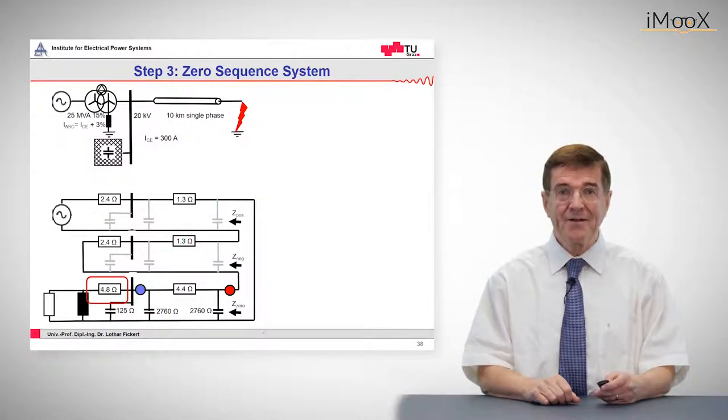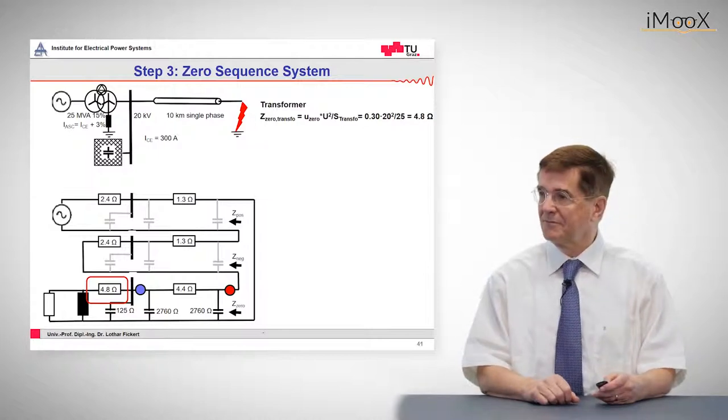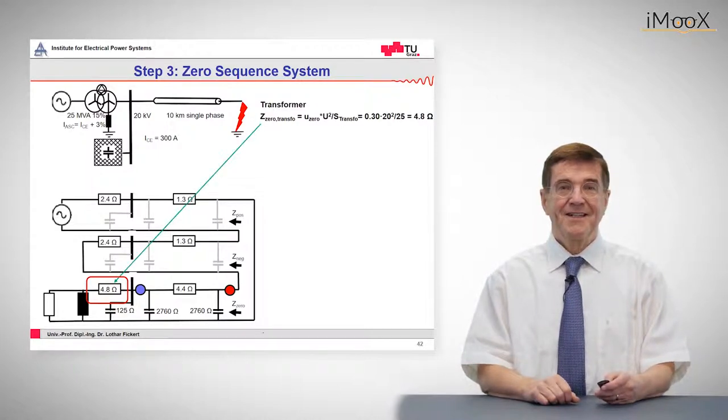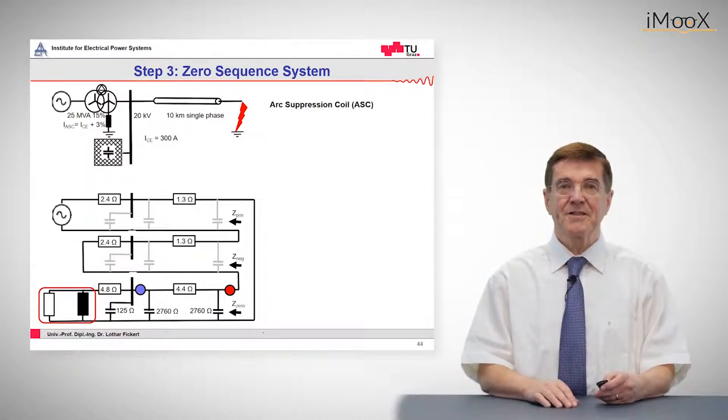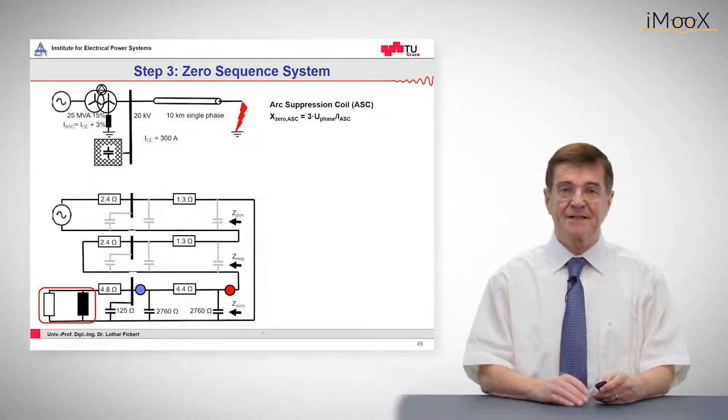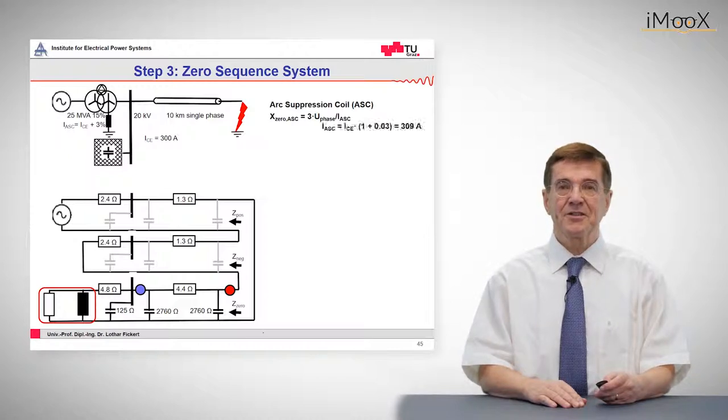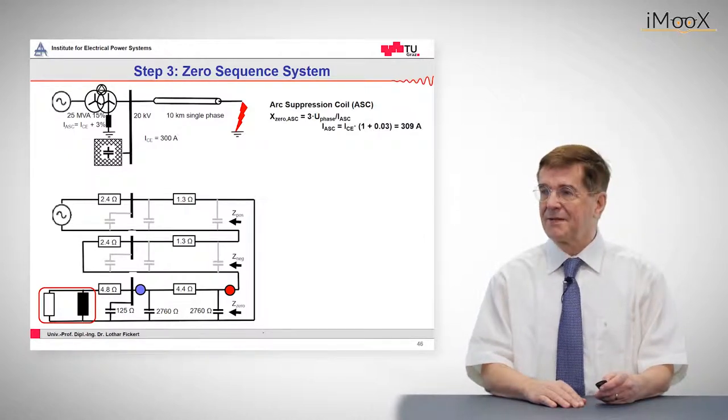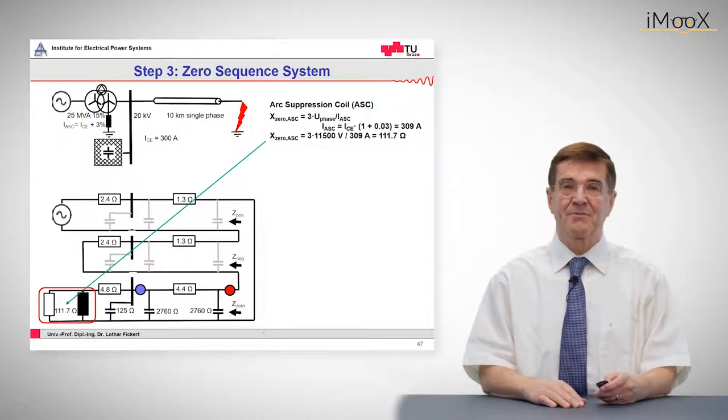So the remaining element now is the transformer. Again we have this well-known formula and it comes out as 4.8 ohms. And now the critical element is the arc suppression coil. The arc suppression coil has again an inductive reactance of three times the phase voltage divided by the current, the nominal current of this arc suppression coil. In this case it comes out as 309 amps, and altogether it's 111.7 ohms.